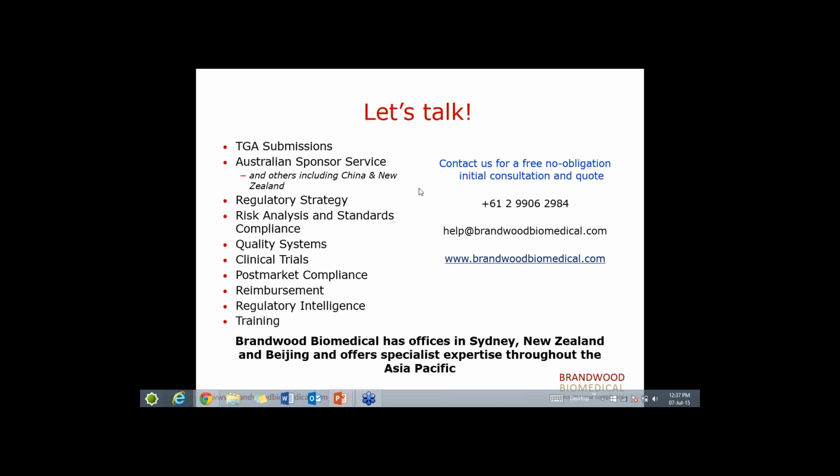The first one I've got here is how similar is the New Zealand medical device acceptance process to the Australian? Okay, so you would have heard an announcement earlier. Well, there were plans to merge the two regulatory entities together under the ANZTPA, which obviously has halted, and that's not progressing. The main difference is that New Zealand accepts overseas certifications from FDA and obviously Europe and Australia. However, Australia does not accept US or FDA approval. Australia only accepts the European. Yes, that's the primary difference between the two.